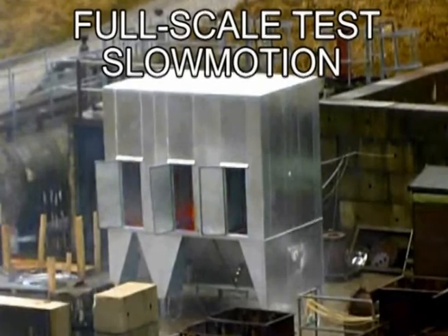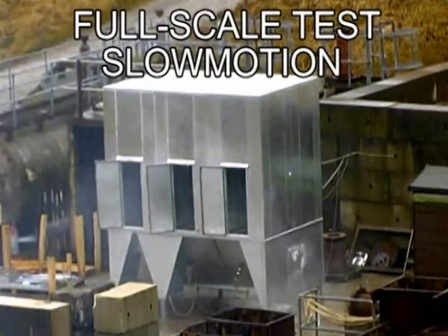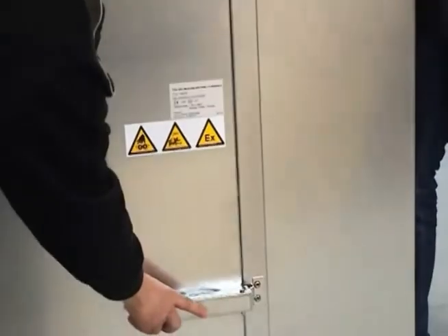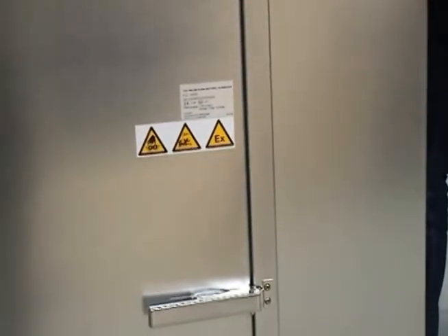Special care is recommended at back pressure flaps, valves, and explosion vents. The explosion doors on wood dust filters will open very early in an explosion event. Some of the doors have a micro switch detecting when a door opens. This immediately stops the filter system and an alarm indicates that an explosion door has opened.